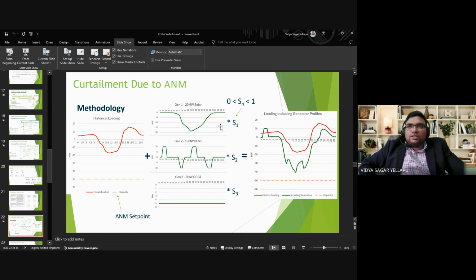So all this generation is to be given a sensitivity factor for that particular asset, which is 50 megawatts in size. And there are three sensitivity factors associated with these three generators. So these three generators impact this particular 50 megawatts asset in their own way. This is the loading, including the generation profiles. When all these things are superimposed together, these are the curves.